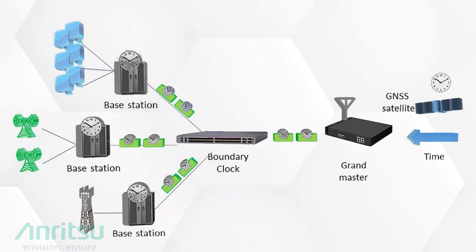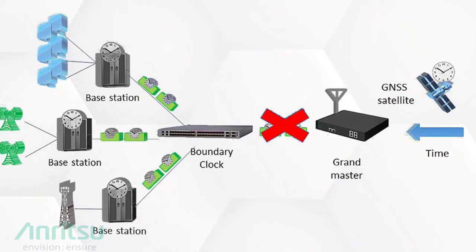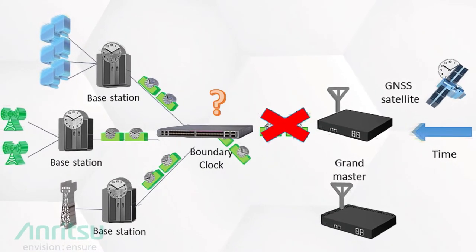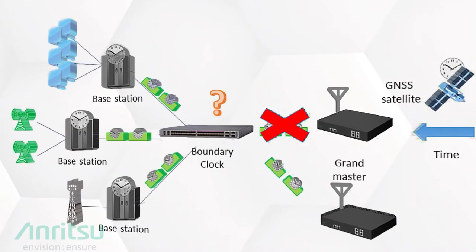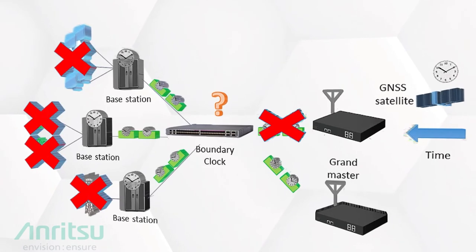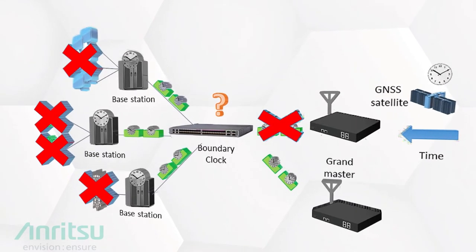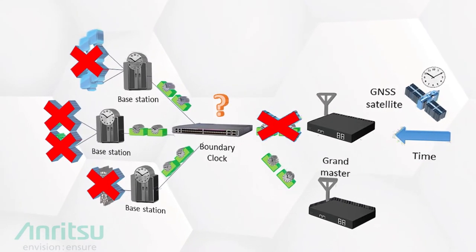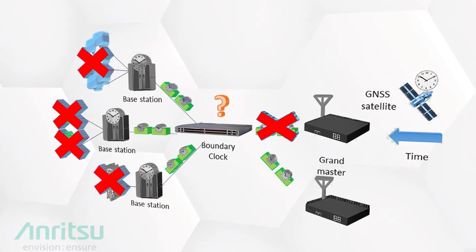It's not until a failover switch or route change due to network conditions causes the boundary clock to lose visibility to an accurate clock source, or an unexpected route change results in timing errors. In some cases, a Grandmaster clock can support hundreds of 5G NR radios, which may be impacted in the event the route and configurations are not tested prior to turn-up.